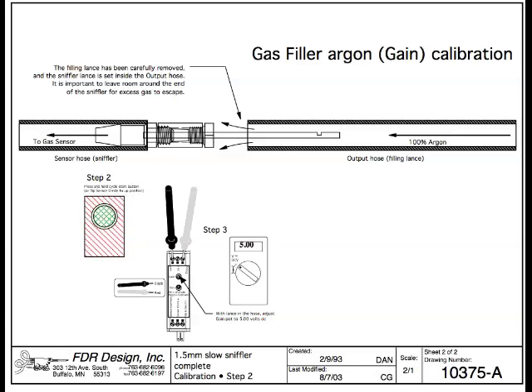So now for this reading, we're going to have to put your DC voltmeter on the 20 function. And your black lead is going to go on common, which is the top left screw terminal. And your red lead is going to go on output, which is the top right screw terminal. You can go ahead and press the cycle start button if it's not already running. And with the machine sucking in 100% argon, you're going to adjust the gain potentiometer until you have 5 volts on your DC voltmeter. When that's done, you can either release the button if you've been holding it, or you can put the sensor override switch down, and the machine should beep and shut off, and now the machine is calibrated for argon. That 5 volts is going to give you a nominal 90 to 93% argon fill, depending on how the machine is set up and if everything's set up correctly.